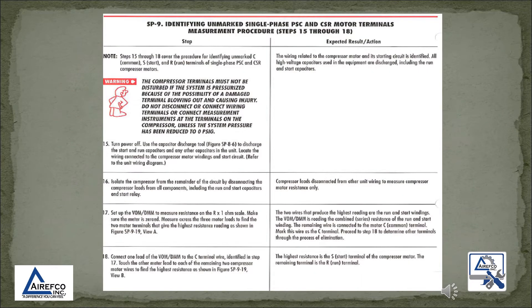This is a page out of one of the service procedures manuals that we sell at Airefco. Please note the warning: the compressor terminals must not be disturbed if the system is pressurized, because of the possibility of a damaged terminal blowing out and causing injury. Do not connect wiring terminals or connect measurement instruments at the terminals on the compressor unless the system pressure has been reduced to zero PSIG.